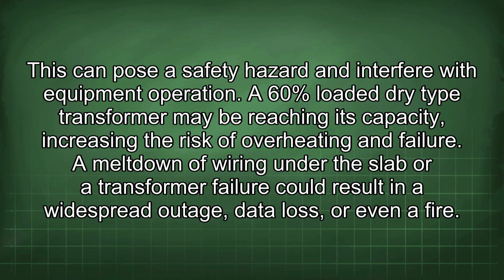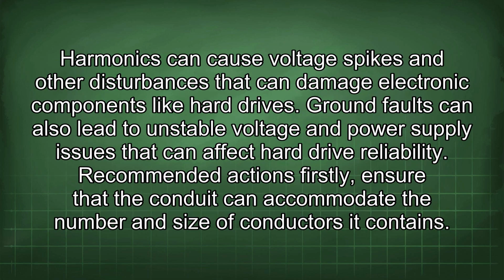A 60% loaded dry-type transformer may be reaching its capacity, increasing the risk of overheating and failure. A meltdown of wiring under the slab or a transformer failure could result in a widespread outage, data loss, or even a fire. Harmonics can cause voltage spikes and other disturbances that can damage electronic components like hard drives. Ground faults can also lead to unstable voltage and power supply issues that can affect hard drive reliability.